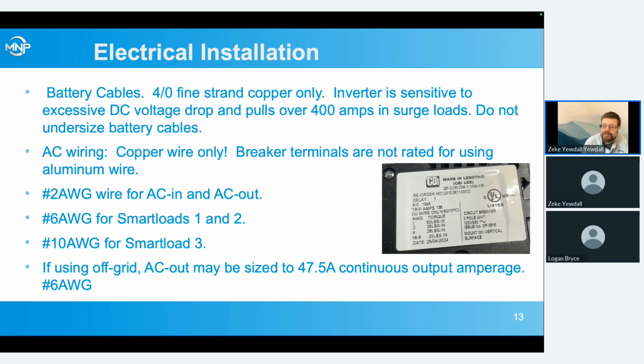Also note that it's only rated for a maximum of 1 gauge wire, so you can't actually get 100 amp rated aluminum wire in there anyway, because that would be 1/0 typically. So yes, you can jam a 1/0 aluminum in that terminal on the breaker, and no, it is not using it according to the listing of either the inverter or the circuit breaker to do that.